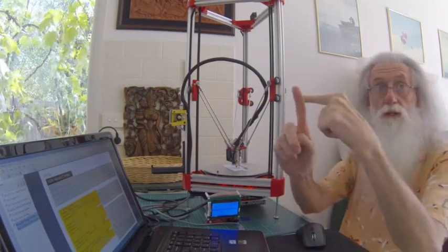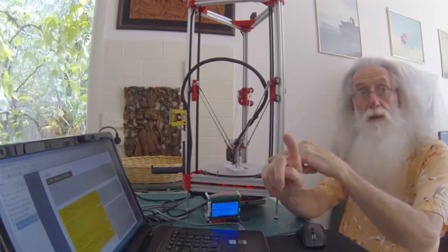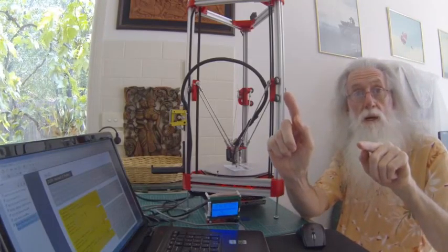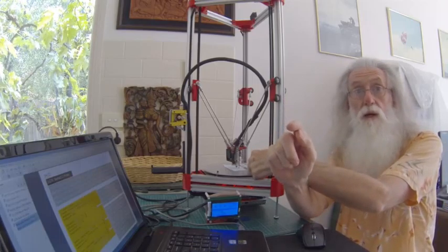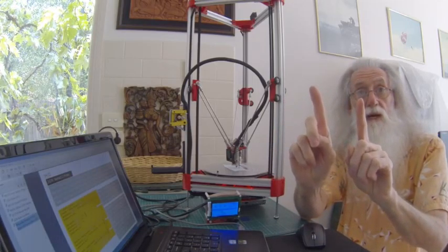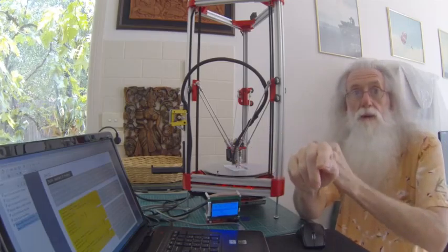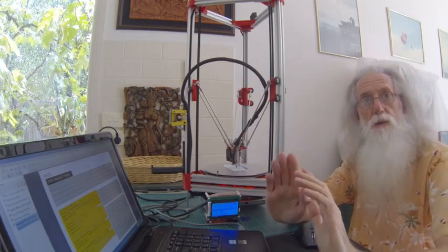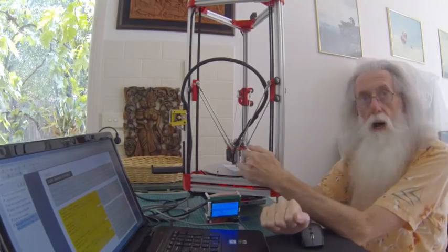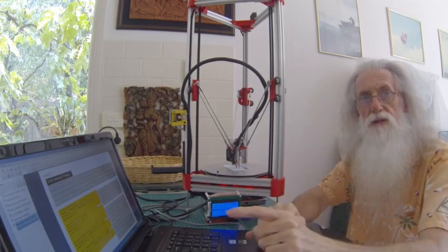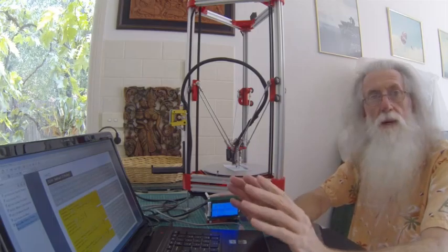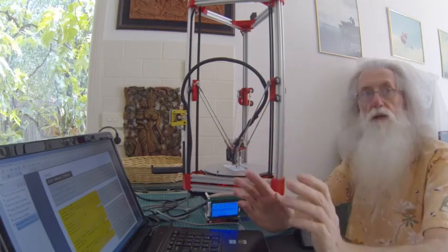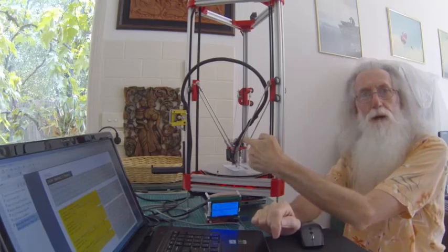So now the cross is where the zero of the bed is, and then the dot over here, or down here, or wherever it happens to be, is the offset of the probe. So you need to set an offset later. You can just measure it off the piece of paper that's stuck to the table. That's why you do all those at the same time. Now, I will need to adjust the X measurement in the config, because mine is not zero. If you put it at the back, it should be zero. But that means your probe housing is lined up, and that screw hole isn't half a mil or a mil off, etc. So that's how you set that position.